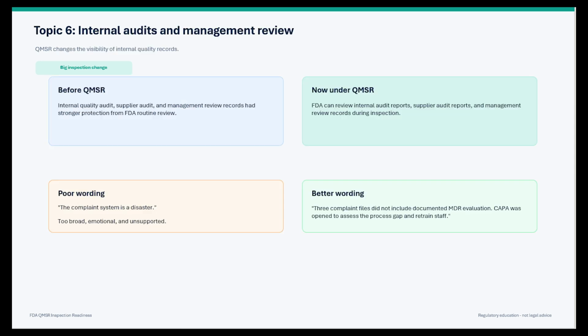The sixth topic is internal audits and management review. This is one of the more important inspection changes under QMSR because it affects the visibility of internal quality records. Before QMSR, internal quality audit records, supplier audit records, and management review records had stronger protection from routine FDA review. Under QMSR, companies should be prepared for the possibility that FDA may review internal audit reports, supplier audit reports, and management review records during an inspection.